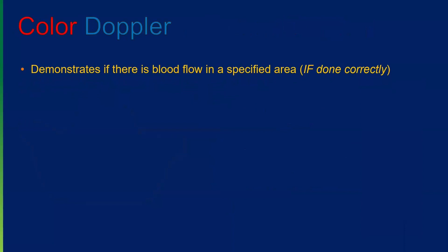In other words, if I'm looking at something like a portal vein and I want to know if the flow is moving into or out of the liver at that point, well, if I turn the color on and I see no flow in that portal vein, I'm going to make some adjustments. I'm going to lower the scale and increase the gain. If when I do those things there still is no flow, then I would be worried that there is no flow in that portal vein. But more than likely, if we're demonstrating no flow, it's just that we haven't set the machine correctly.